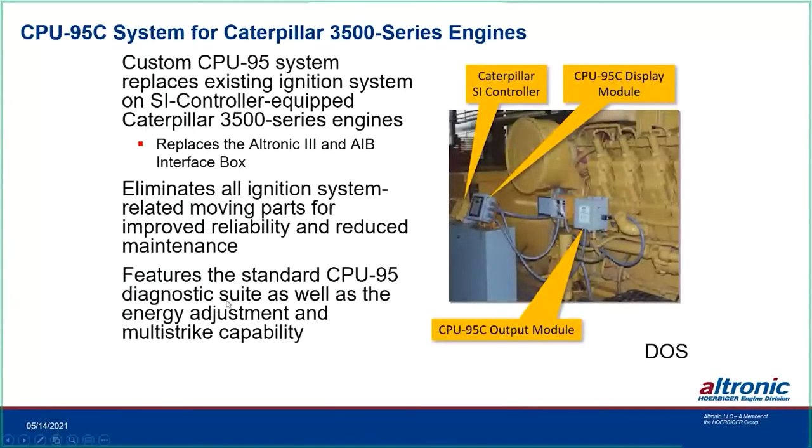The CPU-95C system is for CAT 3500 series engines with the SI controller. Originally these engines had an Altronic III plus an AIB interface box that worked alongside it, still using reset and gear teeth pickups — a hybrid system. The 95C is still available, eliminates ignition-related moving parts, replaces the Altronic III, and adds all the 95 diagnostics, energy adjustment, and multi-strike features.